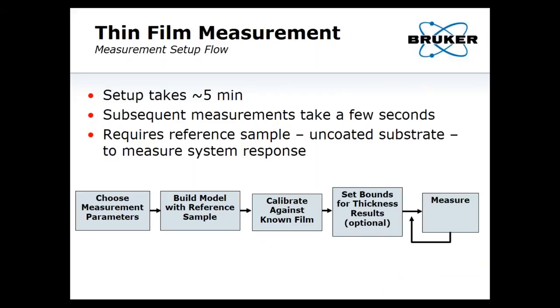For thin film measurements, this is a little more involved. You won't see two sets of fringes on screen because you can no longer trivially segment the top and bottom surface. Setup takes about five minutes. Subsequent measurements take a few seconds and require a reference sample, which is an uncoated substrate of the sort you're using under the film that you're looking at. You use that to measure the system response.